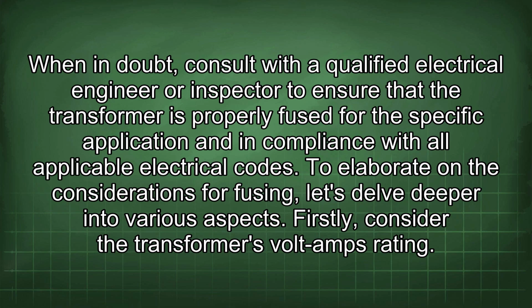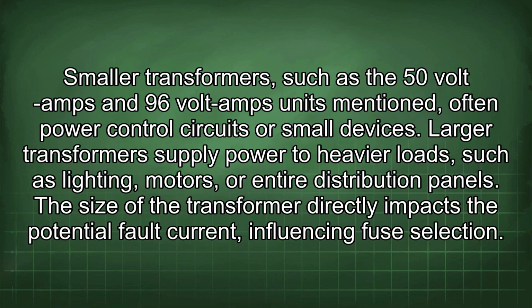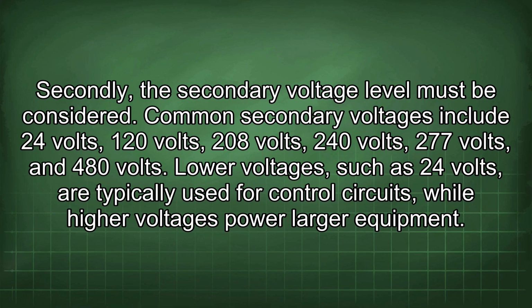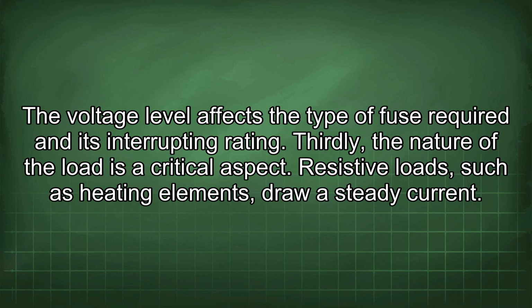To elaborate on the considerations for fusing, let's delve deeper into various aspects. Firstly, consider the transformer's volt-amps rating. Smaller transformers, such as the 50 volt amps and 96 volt amps units mentioned, often power control circuits or small devices. Larger transformers supply power to heavier loads, such as lighting, motors, or entire distribution panels. The size of the transformer directly impacts the potential fault current, influencing fuse selection. Secondly, the secondary voltage level must be considered. Common secondary voltages include 24 volts, 120 volts, 208 volts, 240 volts, 277 volts, and 480 volts. Lower voltages, such as 24 volts, are typically used for control circuits, while higher voltages power larger equipment. The voltage level affects the type of fuse required and its interrupting rating.